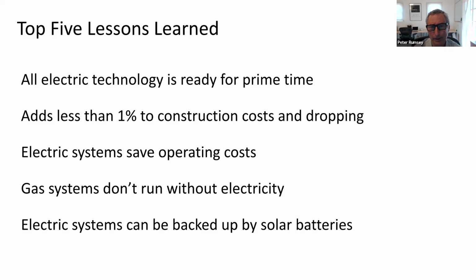The other thing to remember: in California we've had power outages, the power safety shutoffs in the fall when they're worried about wildfires caused by electric lines. Some people say we shouldn't go to electricity because of that, let's stick with gas. The problem is pretty much all gas equipment is now required by code to have safeties and other things that mean it won't run without electricity. That's especially true in commercial buildings. There is no gas heating system that will run without electricity—if nothing else, pumps, but they also need blowers for the combustion chamber and other things. So it's a false sense of security to say we'll stick with gas because of power outages.